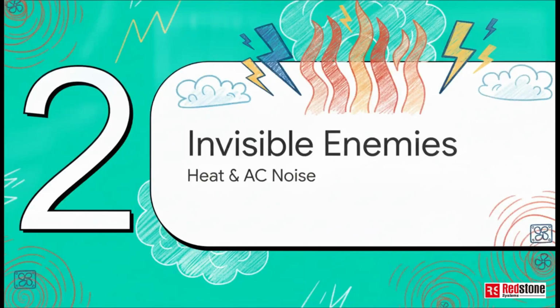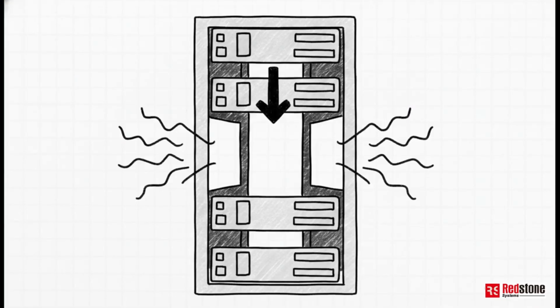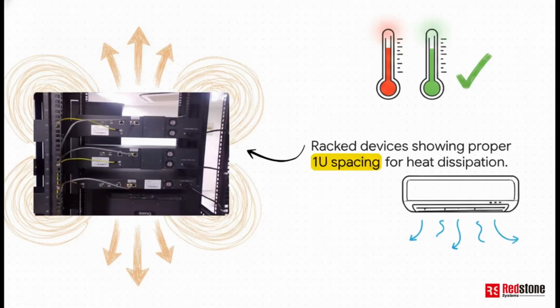Moving right along to part 2, defeating the invisible enemy. It's time to battle heat and AC noise. To actually survive and breathe, your device demands a minimum 1U buffer zone from other equipment. For anyone who might not be super familiar with the terminology, 1U stands for 1 rack unit, which is a standard measurement for server racks, coming in at about 1.75 inches of vertical space. Physical isolation is an absolute must to let the hardware safely dissipate heat. You have to leave those empty slots between the hardware units.